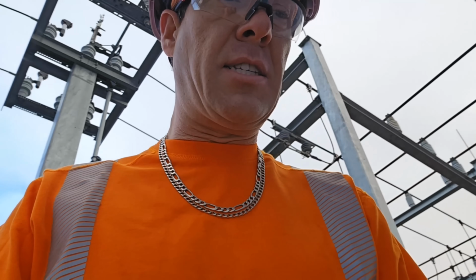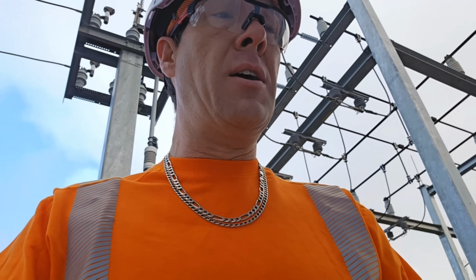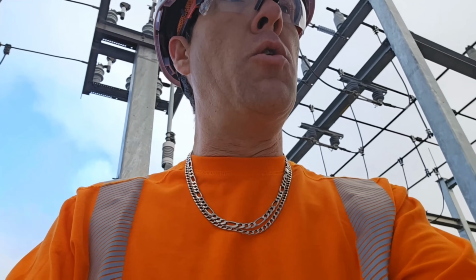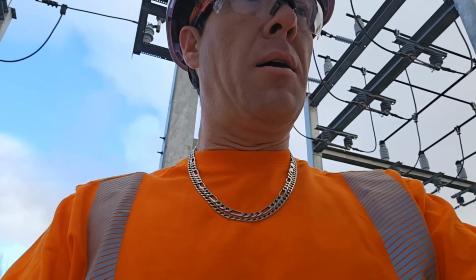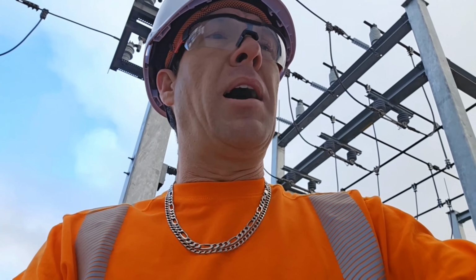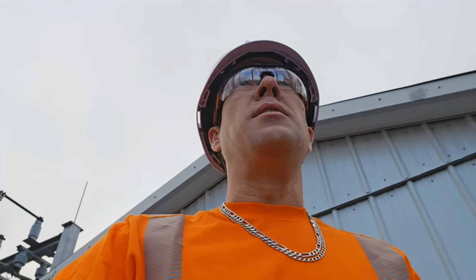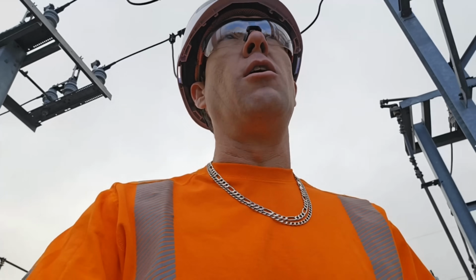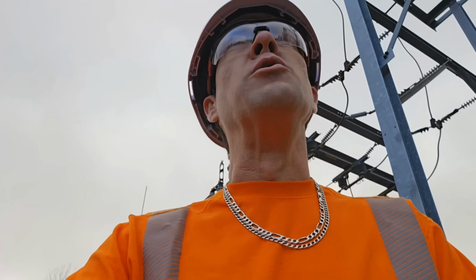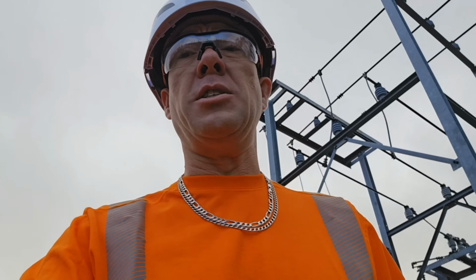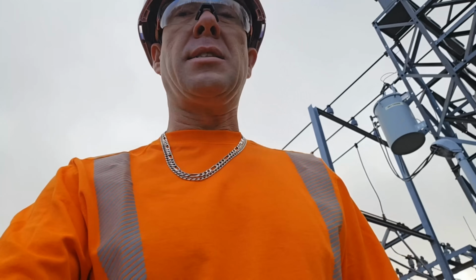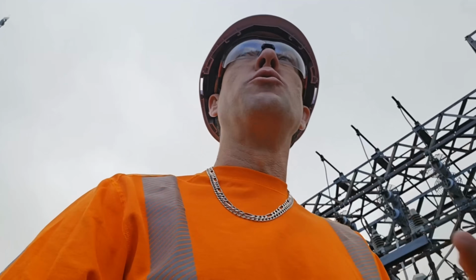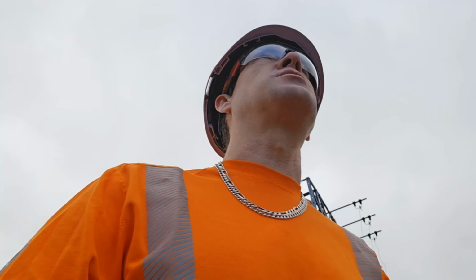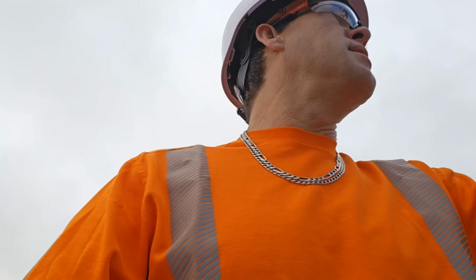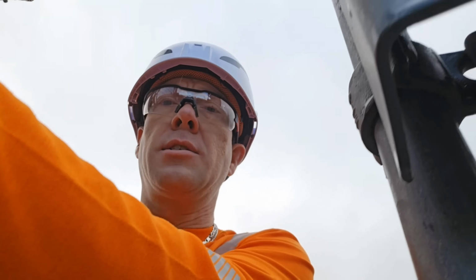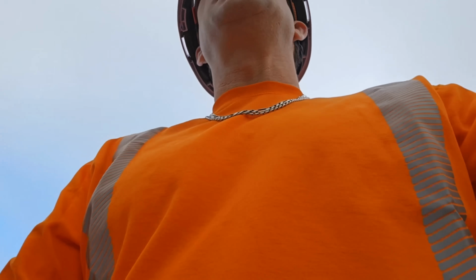We tag the system so that as crews come out into the field, they can see the tags on all the switches to know who operated the device. That device cannot be operated by anyone without first talking to the permit holder, whose information is all on that tag. So the other crews start rolling in. We meet here at the substation and have what we call a tailboard to discuss what steps I've already taken, which crews are out on the road that are going to be working on this job, and we start lining them up to begin the process of switching some feeds around in town.